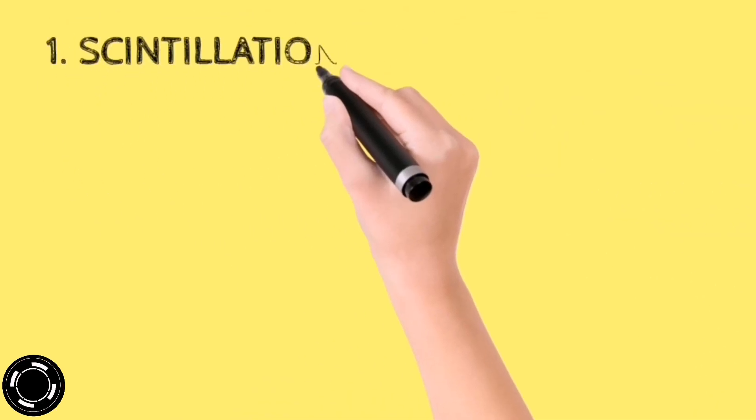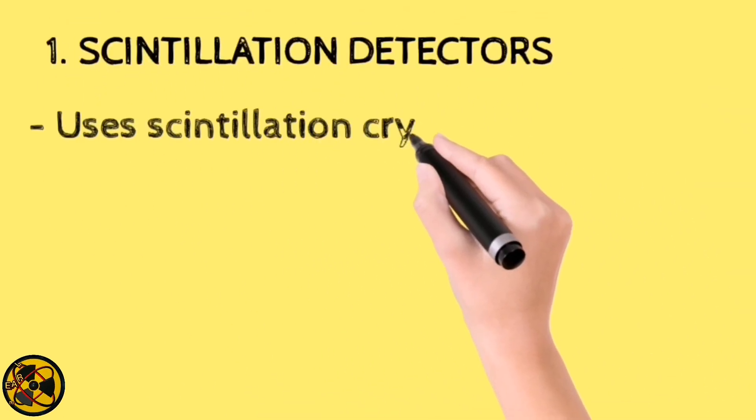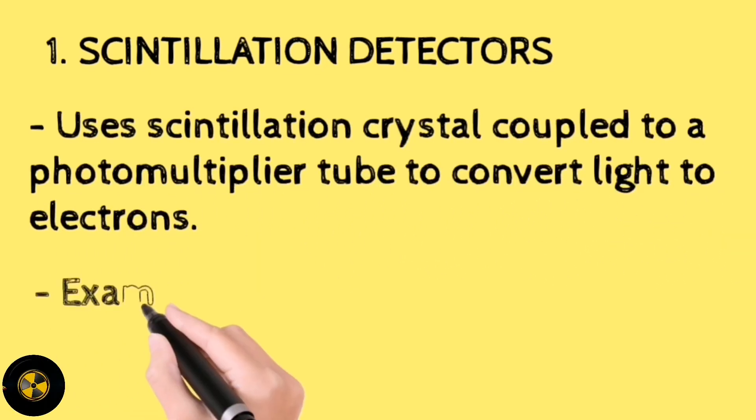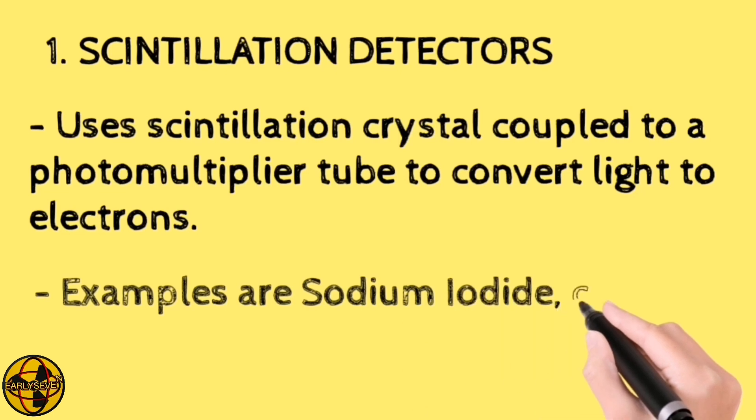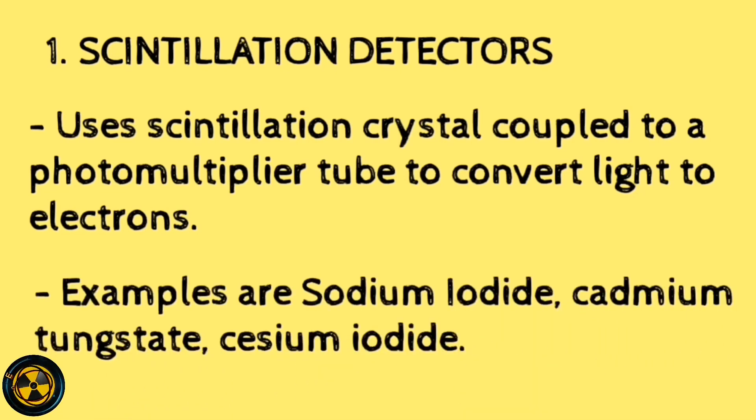There are two types of detectors used in the CT scanner. The first type of detector is a scintillation detector. It uses scintillation crystal, coupled to a photomultiplier tube, to convert light to electrons. Examples are sodium iodide, cadmium tungstate and cesium iodide.